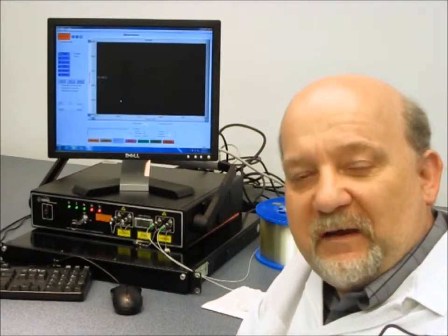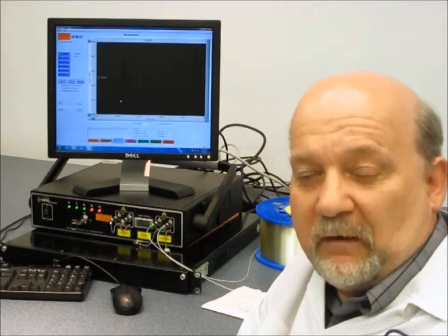For the next demonstration, we're going to try to measure changes in temperature along a section of fiber within a 50 kilometer fiber assembly. So total round trip is 50 kilometers, which would be useful for, say, measuring a 25 kilometer long pipeline, where the fiber has to go out 25 kilometers and then come back 25 kilometers. We're going to show a couple of different variations, beginning with showing you how you make a standard measurement for detecting changes in temperature over a 2.5 meter long section of the fiber.